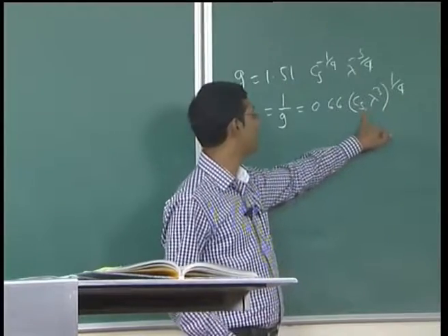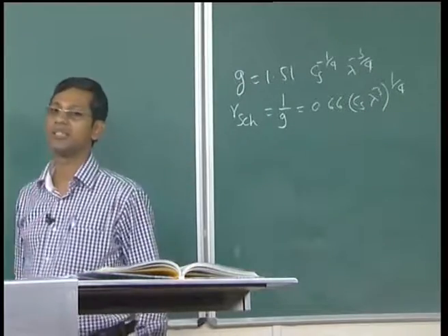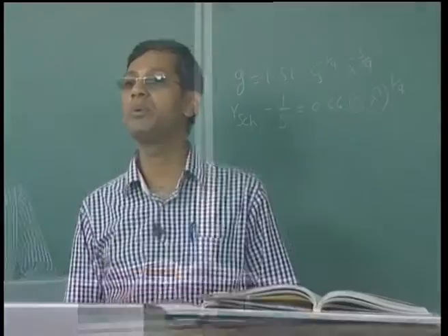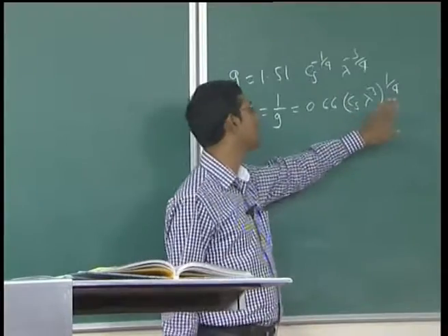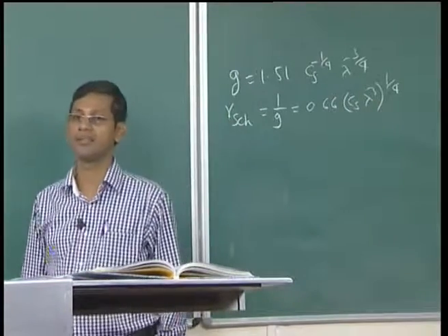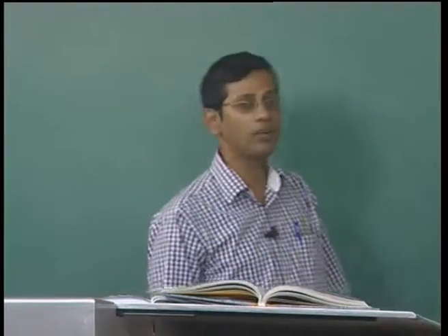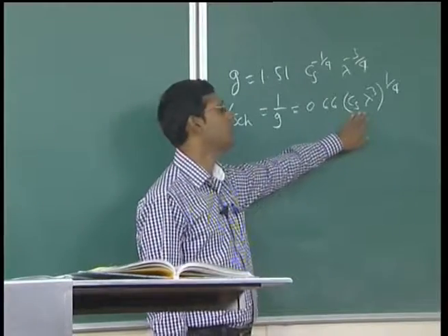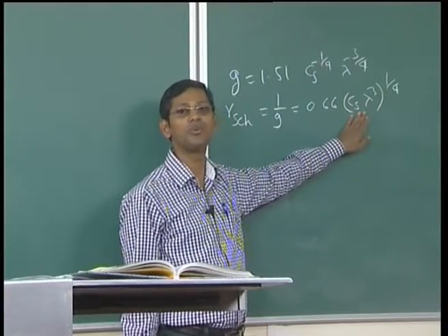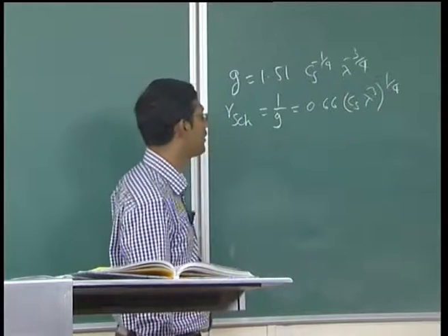By knowing this number, Cs of the objective lens and lambda, we can get that. That is why you now understand why people use million volt electron microscopes, because lambda can be greatly reduced by using higher and higher accelerating voltage, from 100 to 200, 300; people have gone up to 1500 kilovolts actually. Obviously, another way of improving resolution is by correcting the Cs, which you are going to see at the end of the lecture today, how we can do that.